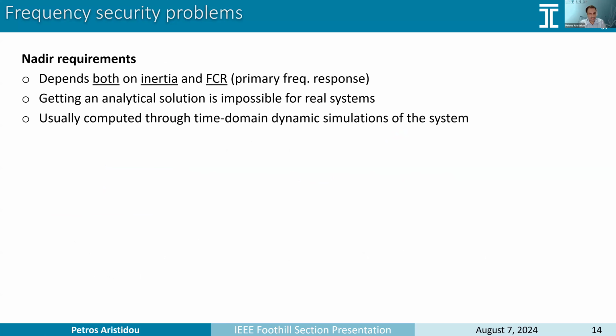Now, if we look into the nadir requirements, for example, the biggest frequency deviation that we allow in the system, there is a little bit of a problem, because the nadir depends both on the inertia and on the frequency containment reserves. So it's not as easy as in the previous two cases, because the RoCoF depended on the inertia, so we could compute it directly. The post-fault steady state relied only on the frequency containment reserves, so we could compute it directly. But here it depends on both of them. On top of that, we cannot find an analytical solution that will directly give us the nadir. So for real systems it is actually impossible, unless you use numerical methods, meaning time domain dynamic simulations, in order to compute this nadir.